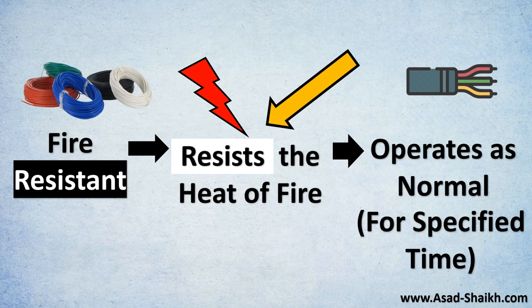It might not work for hours and hours, but maybe for 180 minutes — it depends on the type of cable and insulation selected. For a certain specified time and temperature, it will keep on working as normal even under fire conditions. These cables are usually preferred for emergency shutdown systems where, in case of a hazard, the system has to still work and protect the environment, people, and assets.